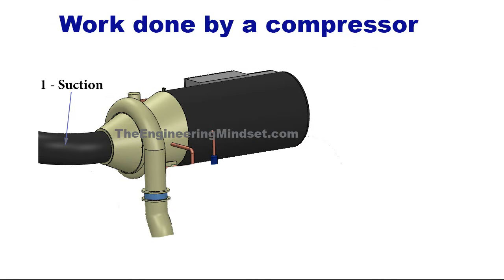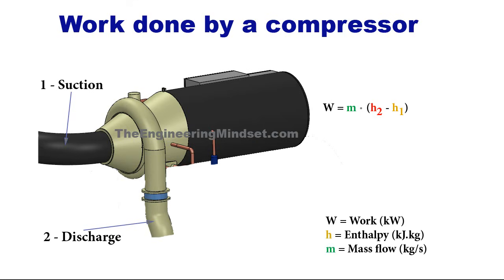So how much work is done by a compressor? Well, you can calculate that, because the energy used is the difference between the suction line and also the discharge line, and it's the difference in enthalpy between the two. And the formula we'll use to calculate this is like this: W equals work measured in kilowatts, H1 and H2 are the enthalpy, measured in kilojoules per kilogram. And then the m, which is the mass flow, which actually should have a dot above it, measured in kilograms per second.